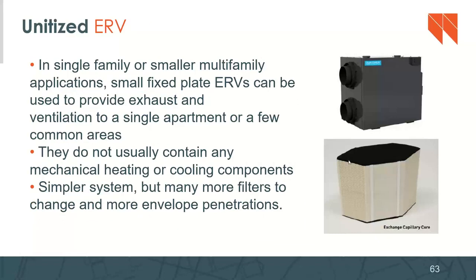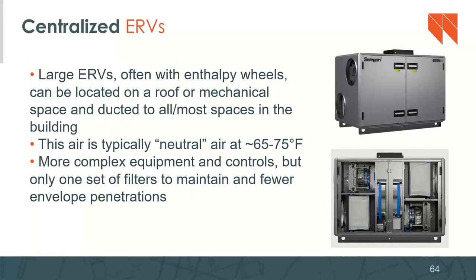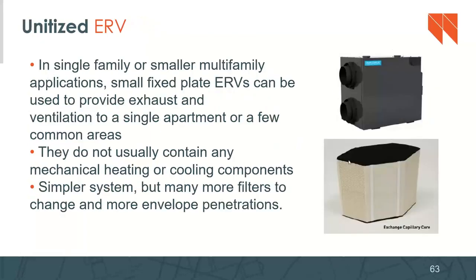So, in terms of the ERV world and what your options are for Passive House, we talk with our project teams about the difference between a unitized ERV and a central ERV. A unitized ERV is a small unit, with enough air for a single family home or a multifamily apartment unit. It's usually a small fixed plate ERV. Usually it's providing exhaust and ventilation to a single apartment. They don't usually contain any mechanical heating or cooling components, except for the case that we talked about with the CERV or the Minotair system. And these can potentially be simpler systems.